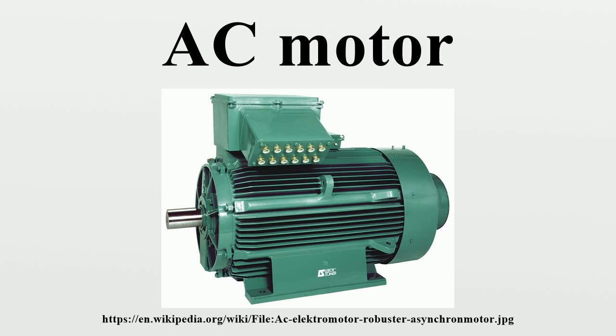An unloaded squirrel cage motor at rated no-load speed will consume electrical power only to maintain rotor speed against friction and resistance losses. As the mechanical load increases, so will the electrical load. The electrical load is inherently related to the mechanical load. This is similar to a transformer, where the primary's electrical load is related to the secondary's electrical load. This is why a squirrel cage blower motor may cause household lights to dim upon starting, but does not dim the lights on startup when its fan belt is removed.